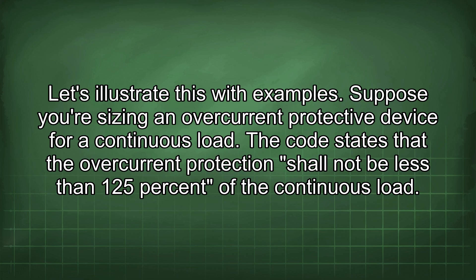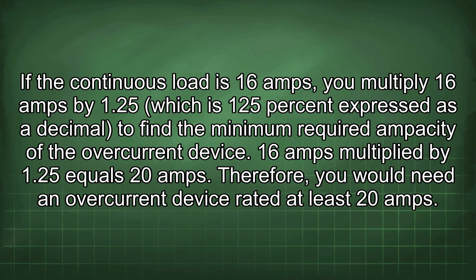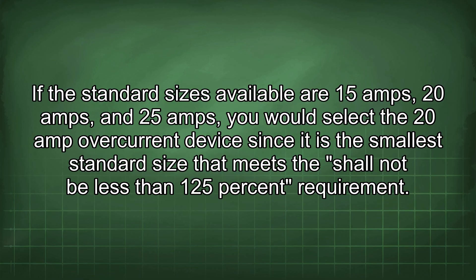Suppose you're sizing an overcurrent protective device for a continuous load. The code states that the overcurrent protection shall not be less than 125% of the continuous load. If the continuous load is 16 amps, you multiply 16 amps by 1.25 (125% expressed as a decimal) to find the minimum required ampacity: 16 amps × 1.25 = 20 amps. You would need an overcurrent device rated at least 20 amps. If standard sizes available are 15 amps, 20 amps, and 25 amps, you would select the 20 amp device.